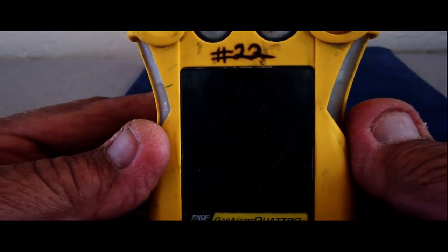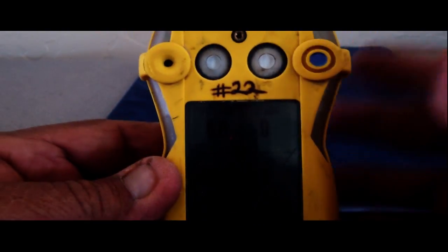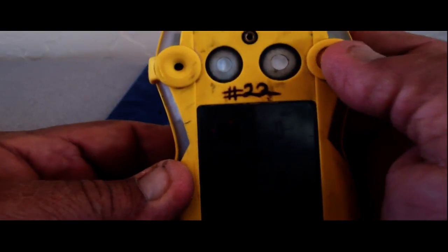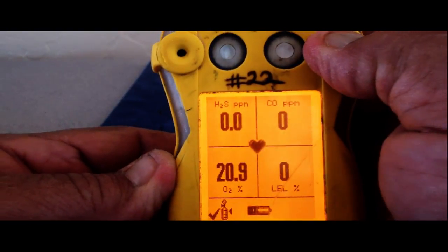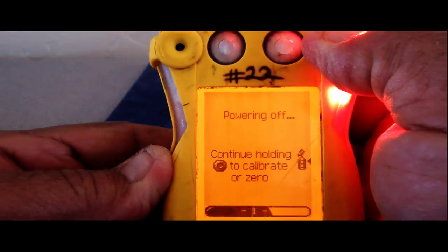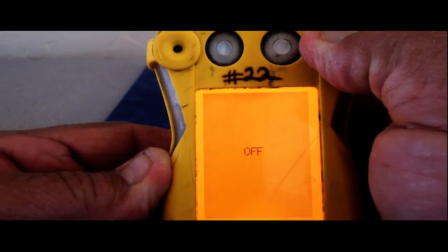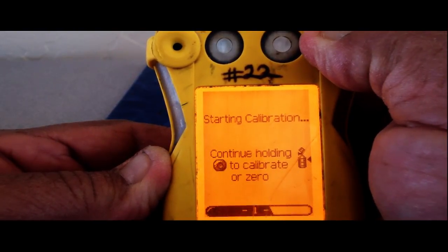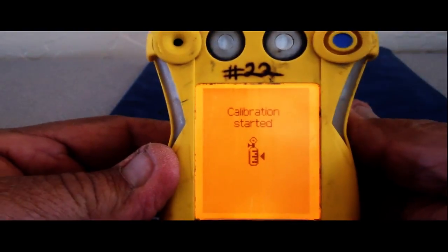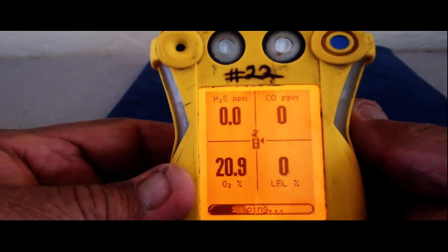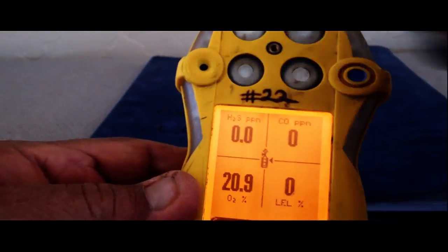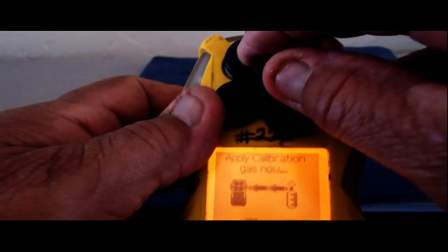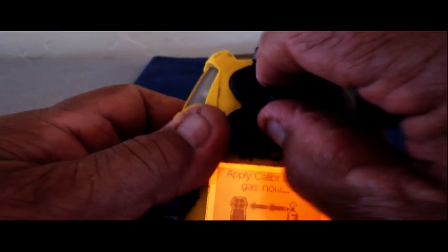To put this meter in calibration mode, we use that same single button, and I'm going to push and hold. Even though it goes through off, I'm going to keep holding. I never let go. And boom, it goes into calibration mode. To calibrate, I apply my gas. I wait to see what it says. I apply my gas, right? I've got to get that screw lined up. That's the trickiest part of it all.